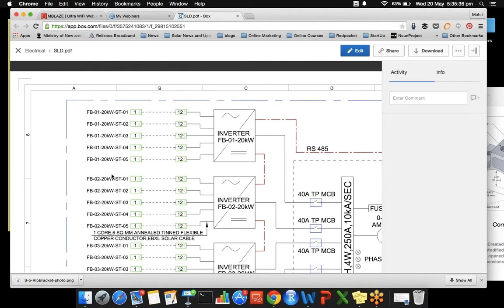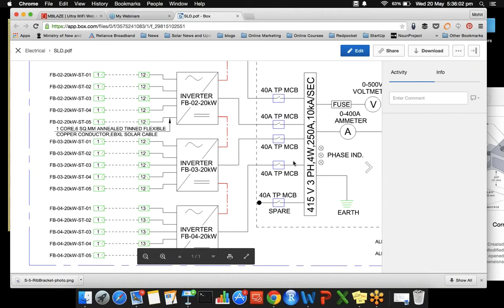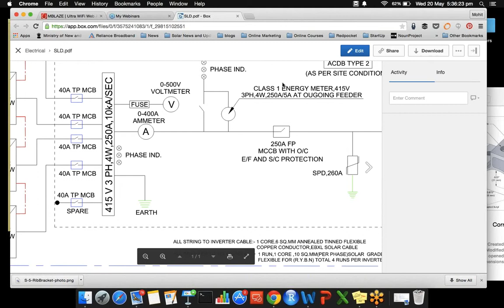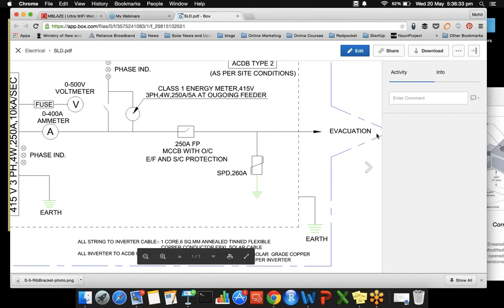This is the SLD diagram that we do for an 80 kilowatt project. As you can see, the green boxes are the inverters. 12 modules are connected in series, and we have 5 such strings connected in parallel for inverter 1. Similarly, for the other 3 inverters, the connections have been made. From the inverters, the connections go to the MCB breaker point, and then from there to the fuse junction. From here, we have a voltmeter to measure the voltage, an ammeter to measure the current, and one connection is given to earthing. Then we have an energy meter to measure the energy generated, another breaker point, an SPD is connected, and then the connection goes to the evacuation point to connect the rest of the appliances.